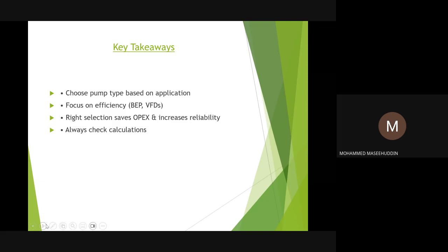So choose pump type based on application. Focus on efficiency with the best efficiency point and the VFDs. The right selection saves the operating cost and increases reliability. And always check calculations, because whenever we do the calculations for the power, for the curve itself, sometimes we are human beings, we might be wrong, but we need to cross check if we have done the proper selection based on our duty conditions or not. That will also really help.